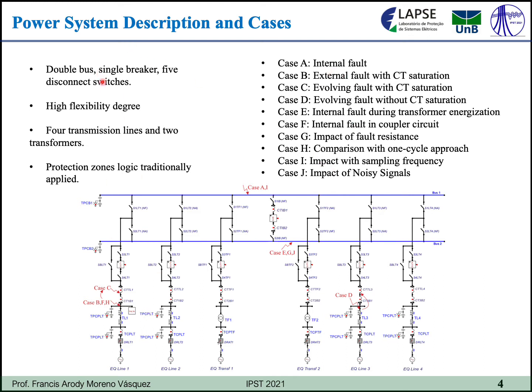Here we use a double bus single breaker, 5 disconnect switches configuration, and this configuration is known for its high flexibility. And here we have 4 transmission lines and 2 transformers. And traditionally, the differential protection implements the protection zones logic. But in our case, as mentioned previously, we don't use this logic.